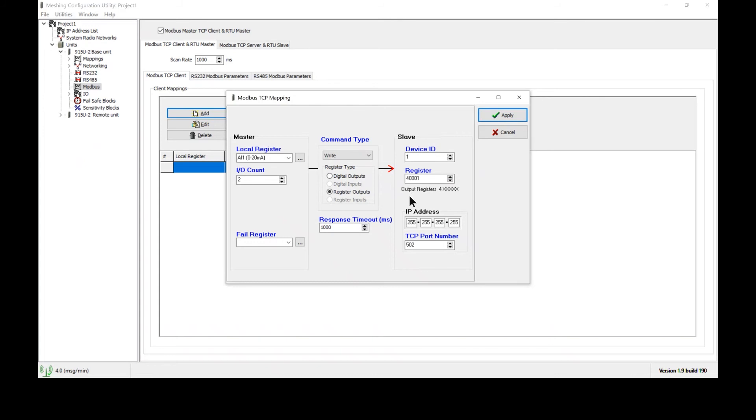As these are 16-bit registers we will need to specify that these are register outputs. They will then be stored at this registered location and of course this can be adjusted to any 40,000 series register on the PLC. The device ID needs to be different from the device ID of the 915. Therefore the PLC must be configured with a device ID of 2 or higher.